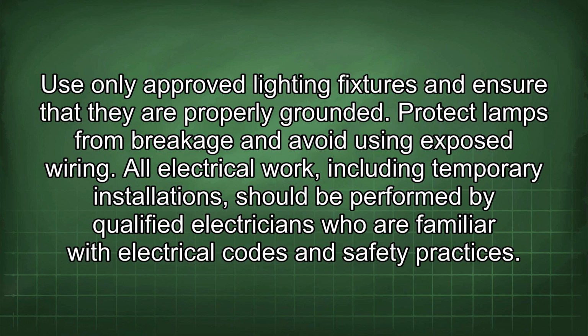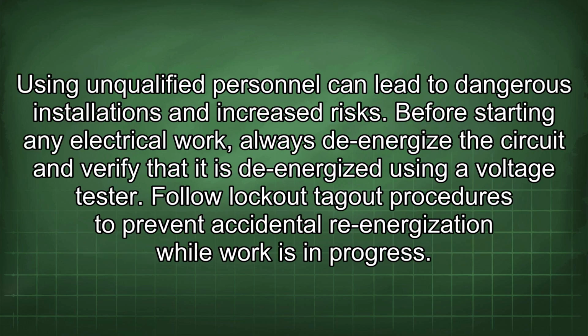All electrical work, including temporary installations, should be performed by qualified electricians who are familiar with electrical codes and safety practices. Using unqualified personnel can lead to dangerous installations and increased risks. Before starting any electrical work, always de-energize the circuit and verify that it is de-energized using a voltage tester. Follow lockout-tagout procedures to prevent accidental re-energization while work is in progress.